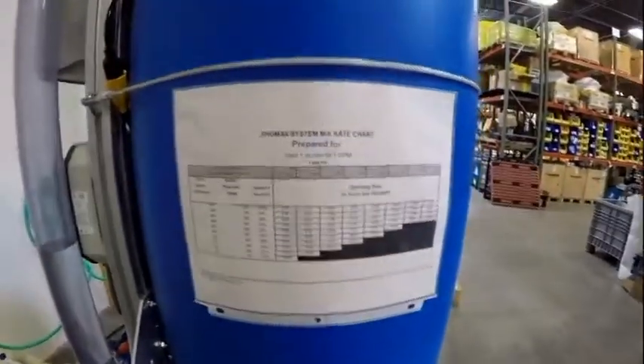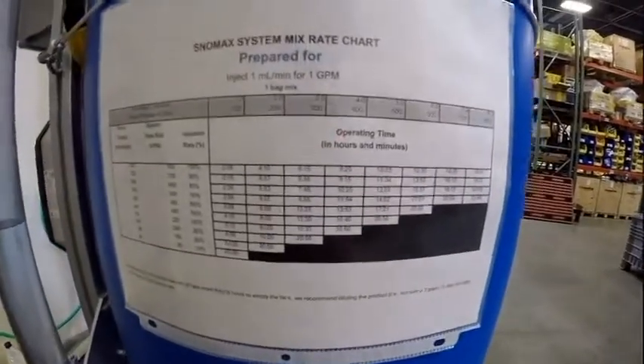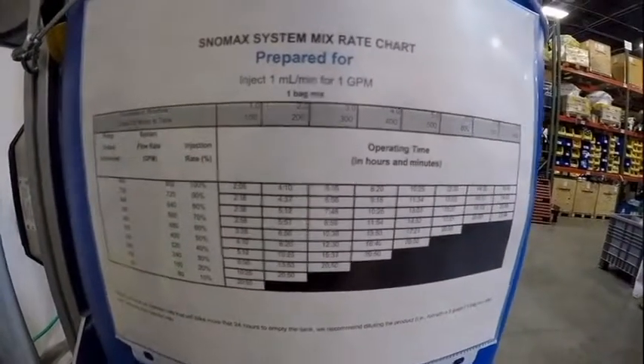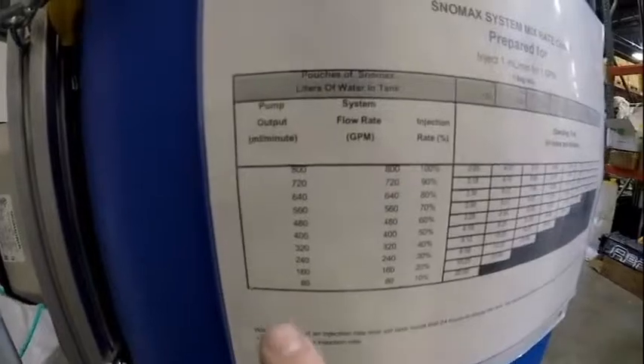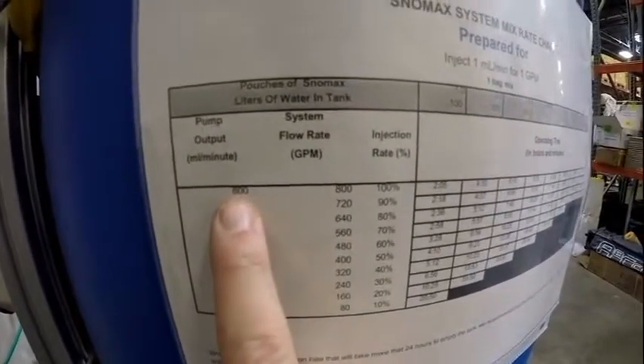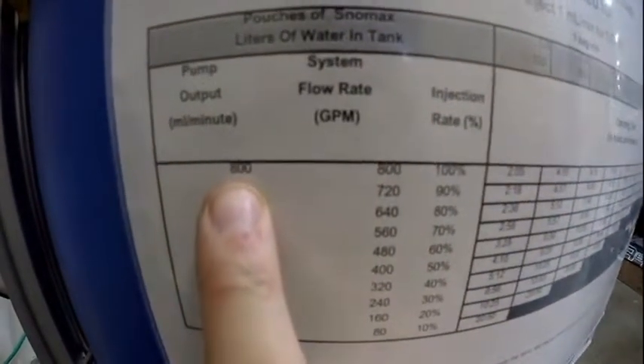Next, we're going to take a look at your mix chart that was provided by your Snomax rep. For this specific customer, their max flow is 800 gallons a minute with a total of a 1-to-1 mixture, so we're going to calibrate for 800 milliliters a minute.